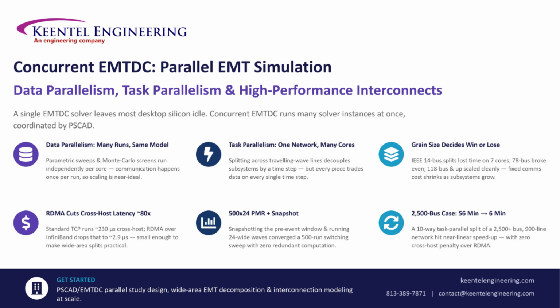Task parallelism is different. It splits one network across multiple cores using the traveling wave lines as natural decoupling points, but every subsystem has to trade data on every single time step. That's why grain size decides whether this actually pays off. A small 14-bus system split across 7 cores actually lost time. A 78-bus case broke even, and anything from 118 buses up scaled cleanly, because the fixed communication cost shrinks relative to the work being done.